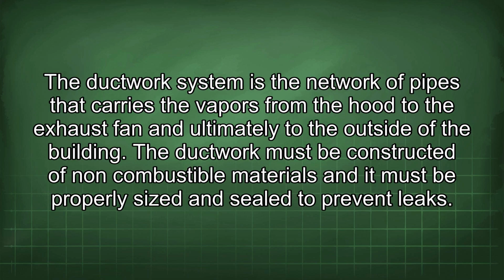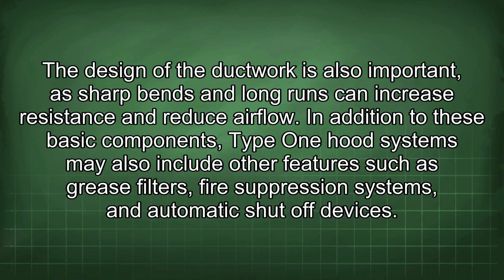The ductwork system is the network of pipes that carries the vapors from the hood to the exhaust fan and ultimately to the outside of the building. The ductwork must be constructed of non-combustible materials, and it must be properly sized and sealed to prevent leaks. The design of the ductwork is also important, as sharp bends and long runs can increase resistance and reduce airflow.